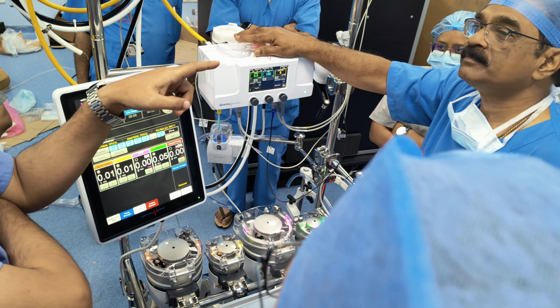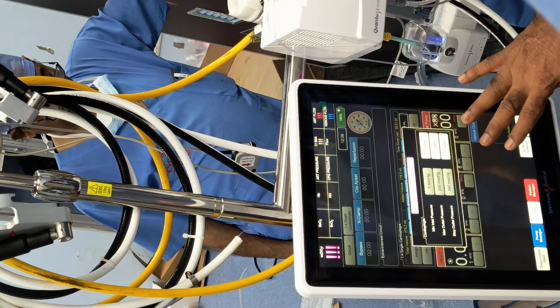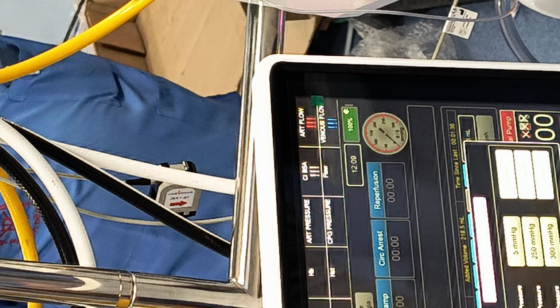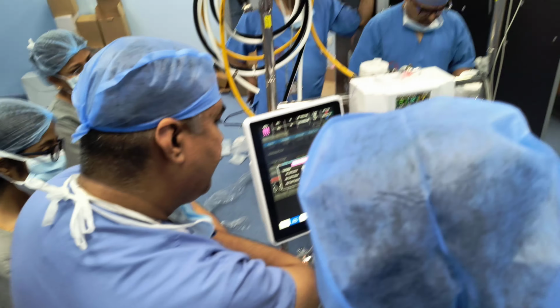You click in the middle of it, you'll get the pressure received. Now, as you know, for cardioplegia, if you want to start cardioplegia, your arterial pump needs to be moving every time, right? Otherwise, what will happen? If you start cardioplegia when the arterial pump is off and you are connected to the patient, you will draw blood out from the oxygenator and create negative pressure, right? It's called the cerebral steal.